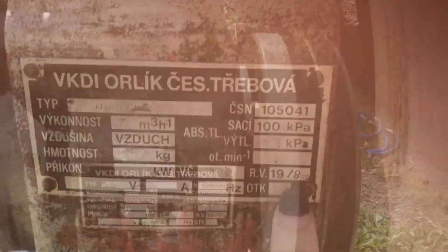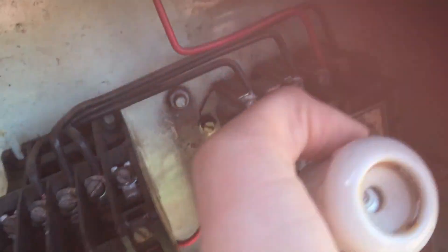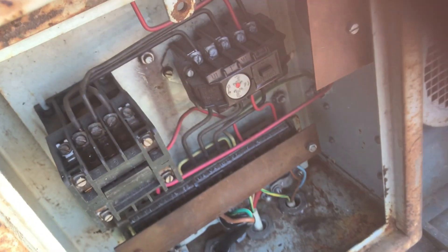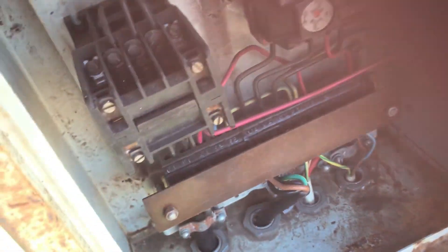It's really old, as you can see. At first it looked like it was just this fuse, and yes it has some water damage, but it wasn't just a fuse — this contactor is totally blown, as you can see.